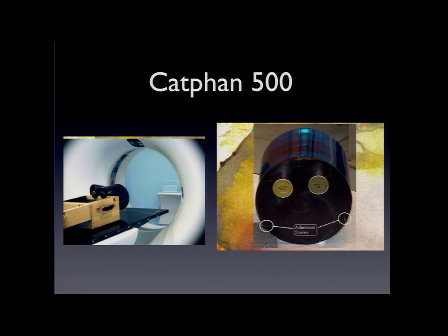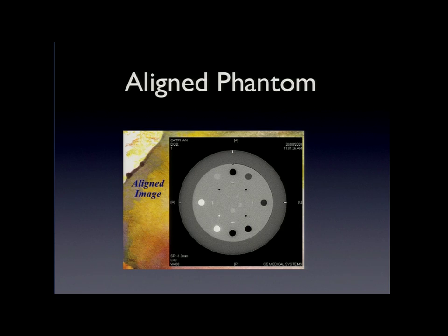The Catphan, you can also do these same things. You hang it off the box it comes in over the edge of the table. That's what it hangs on, these rods back here, and then you have these positioning screws that help you to adjust the pitch and the yaw, depending on what you need to accomplish to align it.